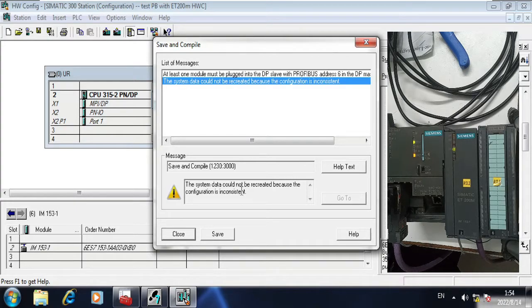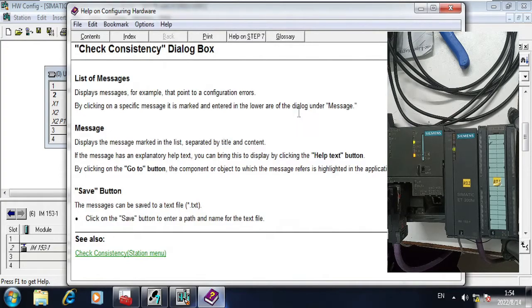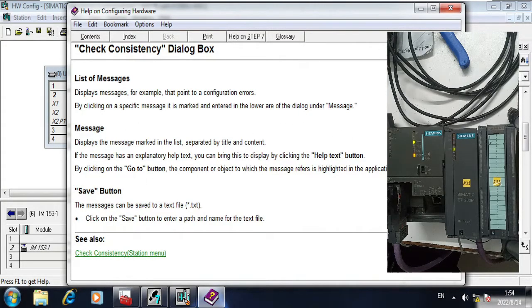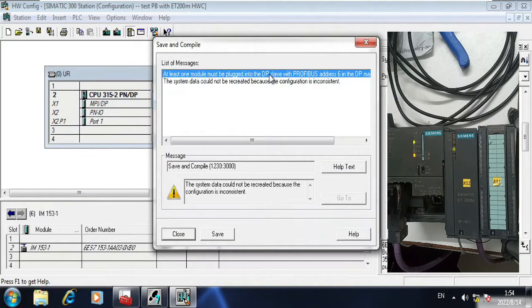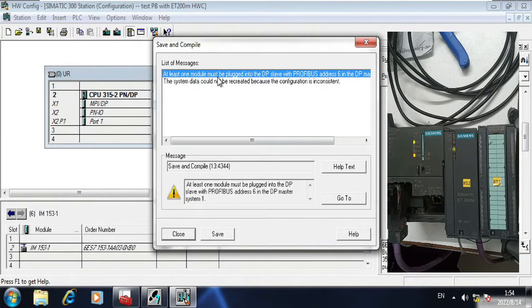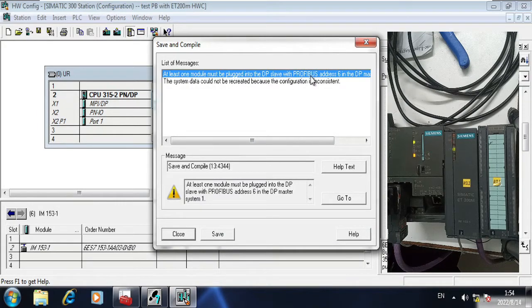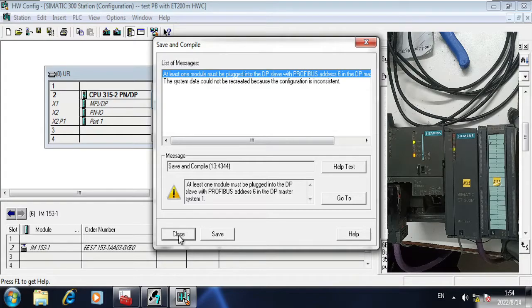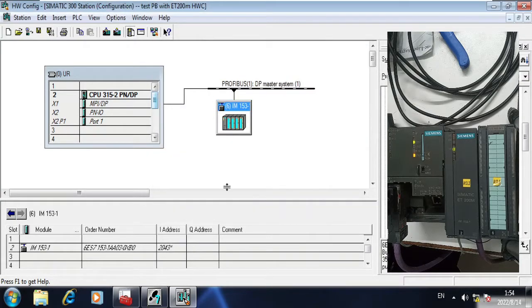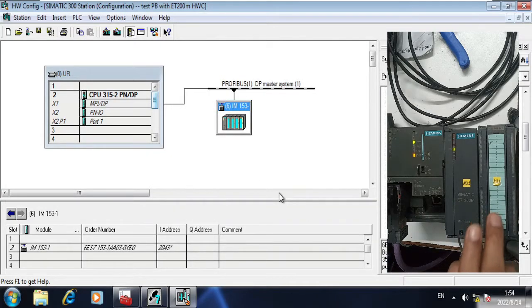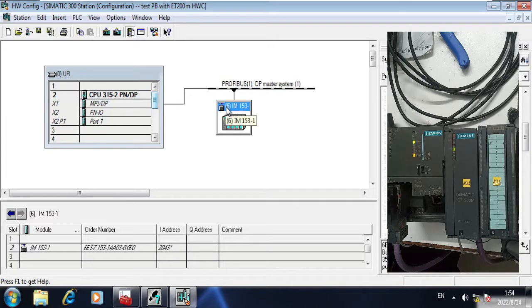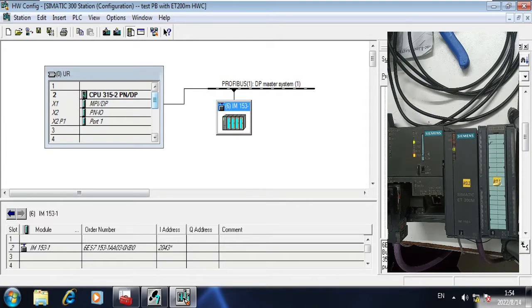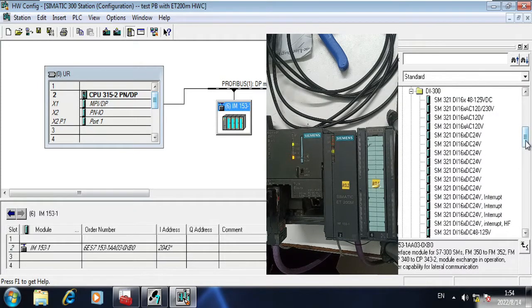But go to help and above you can see here, at least one module must be plugged into the DP slave with Profibus. So that was what I have told you before, that we must have to at least connect one module with ET200. So my module is DI 32.